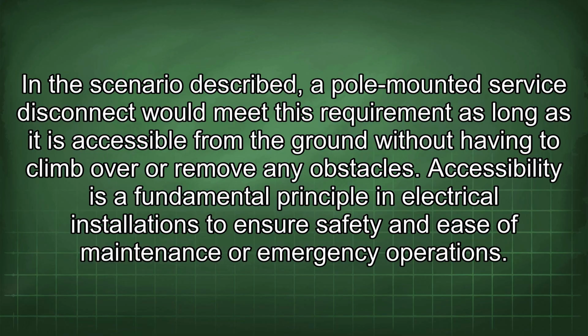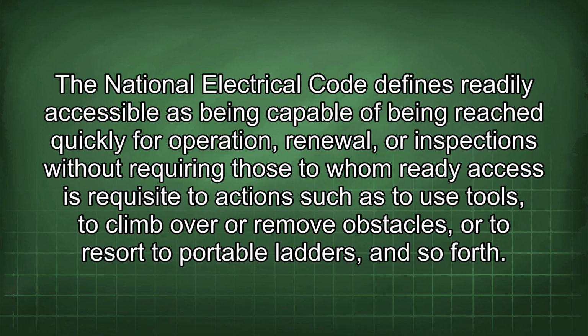Accessibility is a fundamental principle in electrical installations to ensure safety and ease of maintenance or emergency operations. The National Electrical Code defines readily accessible as being capable of being reached quickly for operation, renewal, or inspections without requiring those to whom ready access is requisite to actions such as to use tools, to climb over or remove obstacles, or to resort to portable ladders, and so forth.